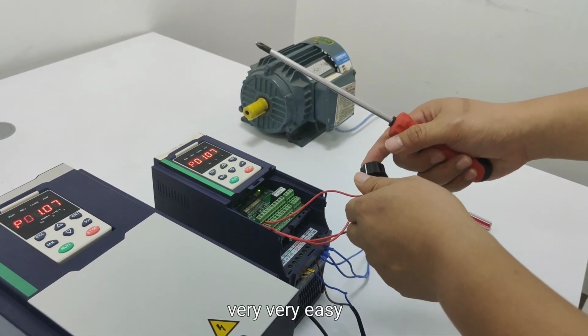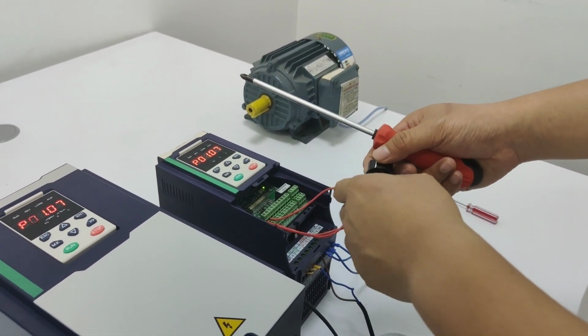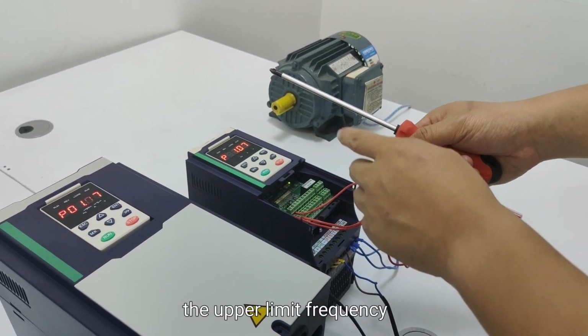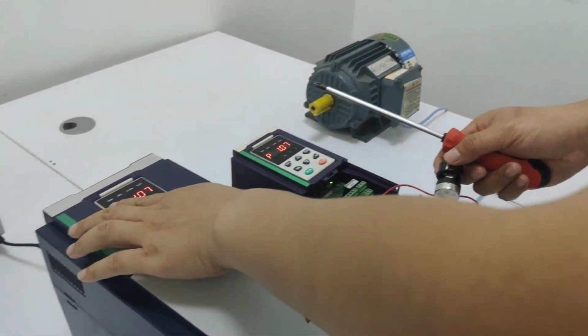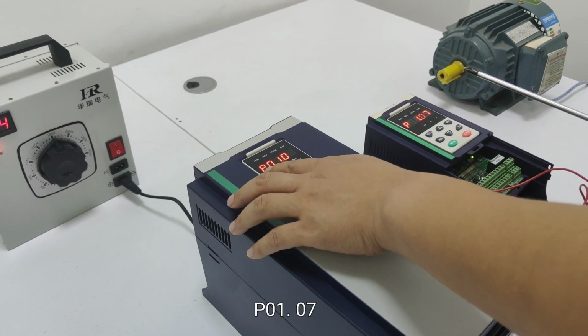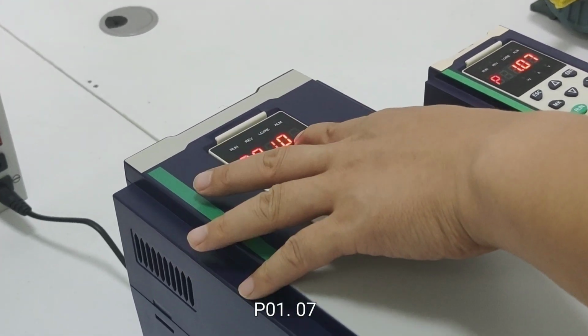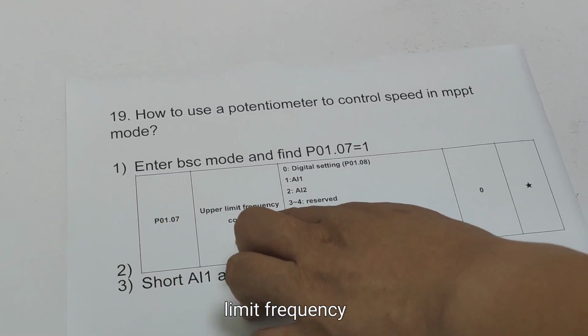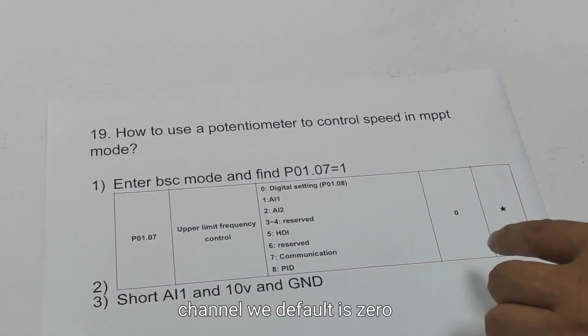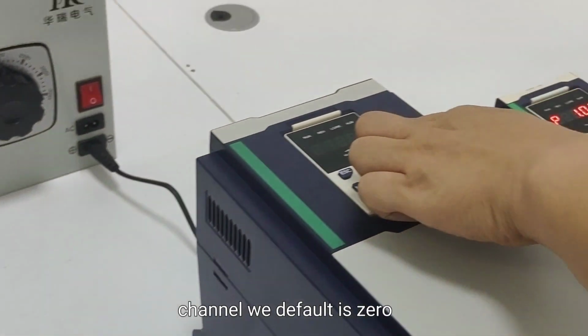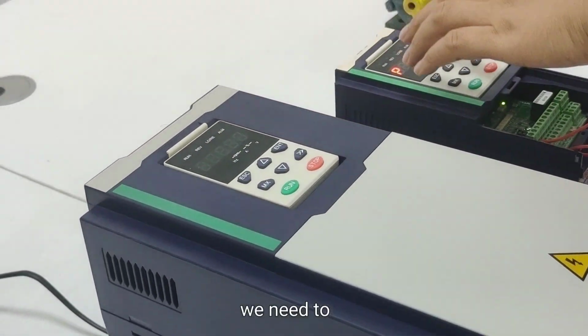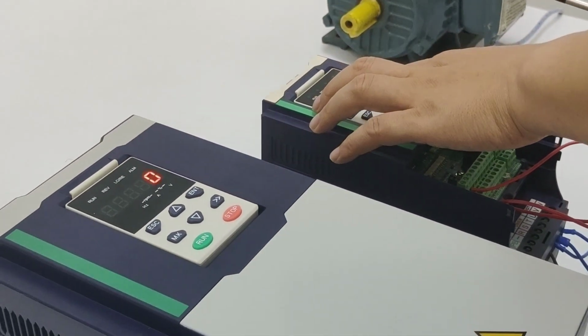It's very easy. For example, the upper limit frequencies. This parameter P01.07, up limit frequency channel. The default is 0. We need to choose 1. Okay?